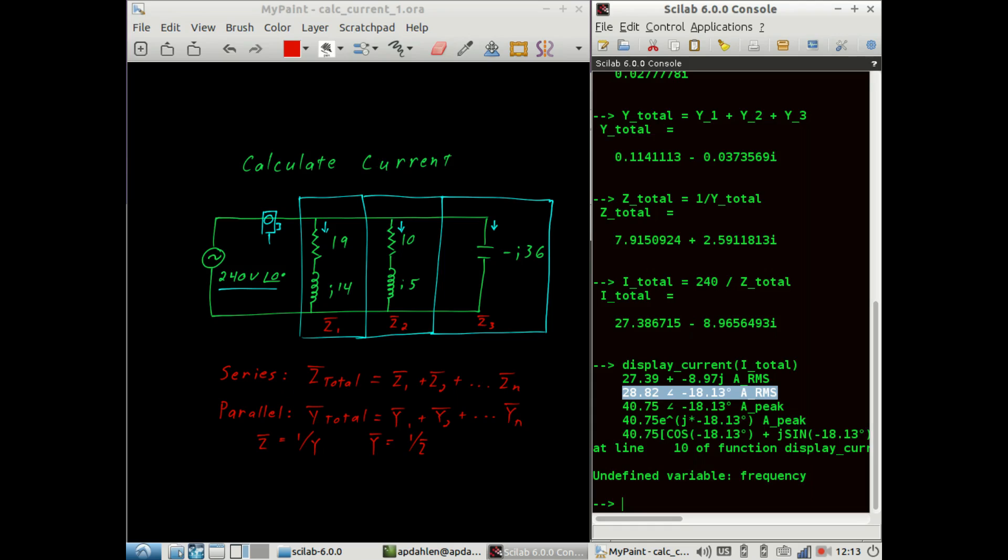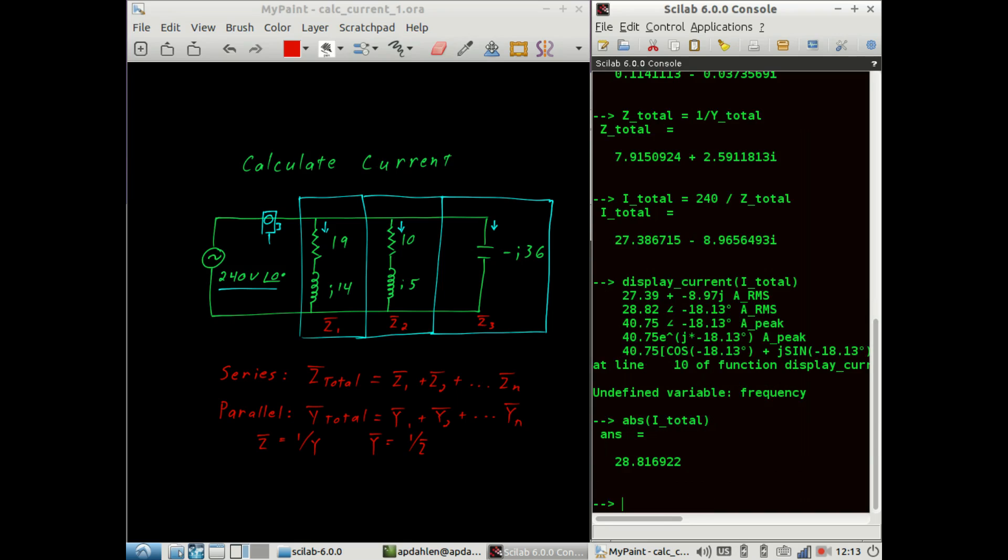And here we see the most important number. So the RMS value of that particular phasor is 28.8 amps. You could also just say the absolute value of the total current, again, about 29 amps.